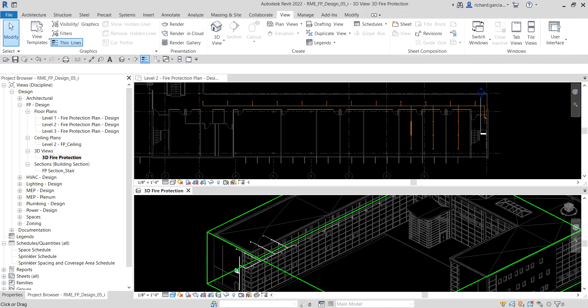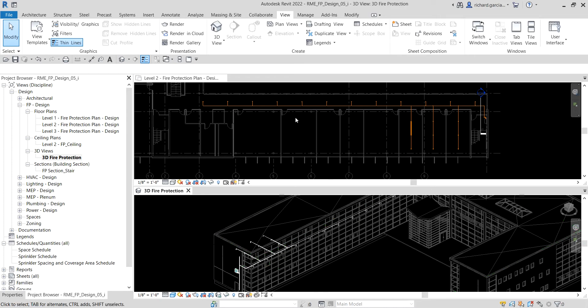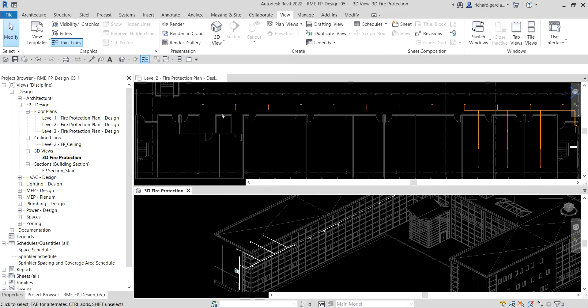Now we are going to modify the diameter of the fire protection pipe run. The majority of the pipe segments service no more than two sprinklers, and because the design specifications require a one-inch diameter for pipes servicing two sprinklers, it is more efficient to specify one-inch diameter for all pipe runs and then adjust the branches servicing more than two sprinklers separately.